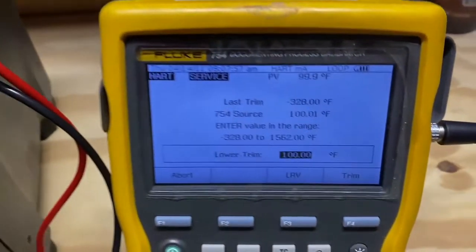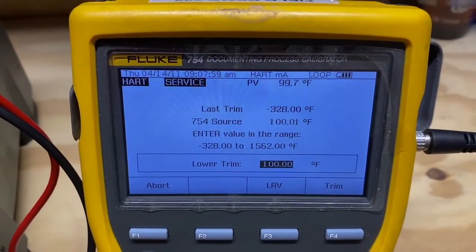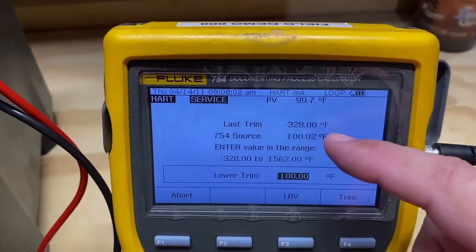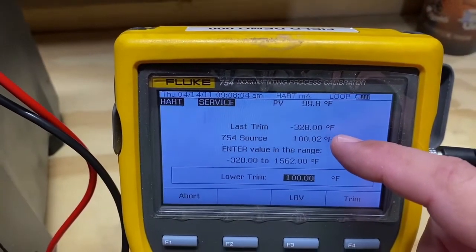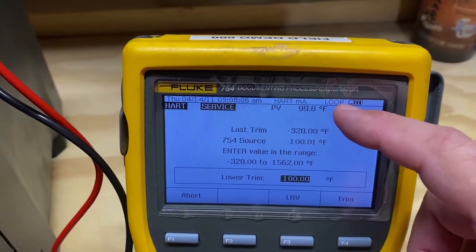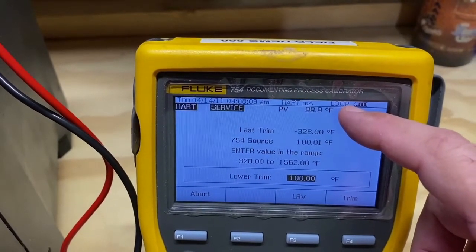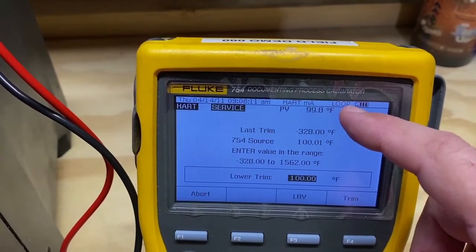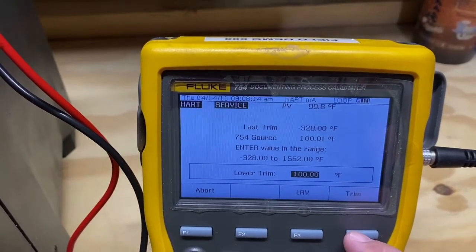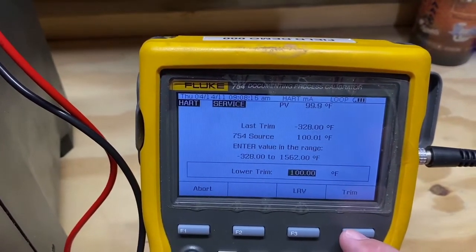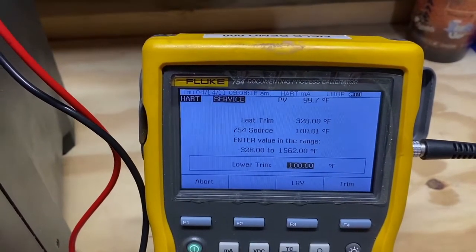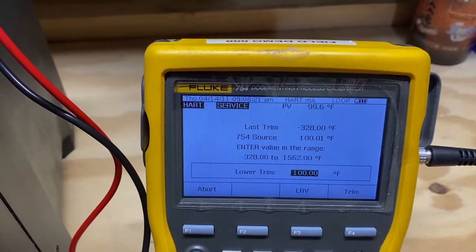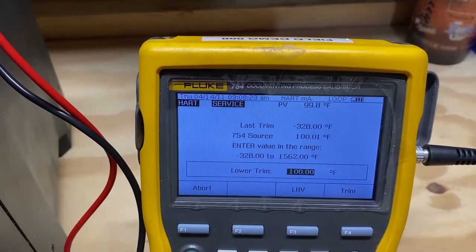The 754 at that point will monitor the 9144 temperature against the digital temperature being output as the PV from the transmitter. By pressing the trim button, you can make a very accurate adjustment to align the LRV of both the actual temperature and the transmitter PV.